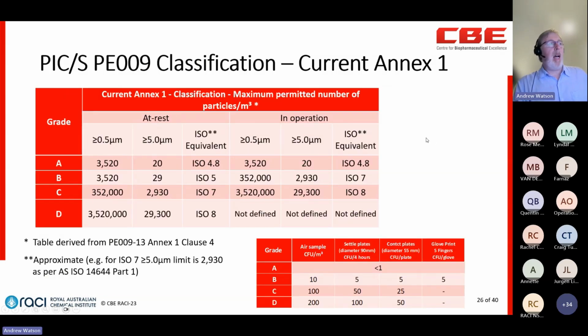This is translated from ISO class into a grade, particularly for the manufacture of sterile goods. So this is what's in the current Annex 1. I've got both here, the particle concentrations and the equivalent in ISO. Within grades A, B, and C, there is an at-rest component and an in-operation component. So if you've got a grade C clean room, you will test the clean room twice. Once at rest, in which we expect it to meet an ISO 7 standard, and once in operation, where we expect it to meet an ISO 8 standard.